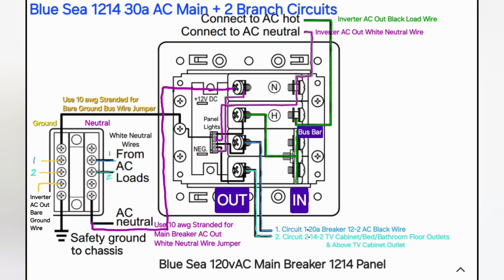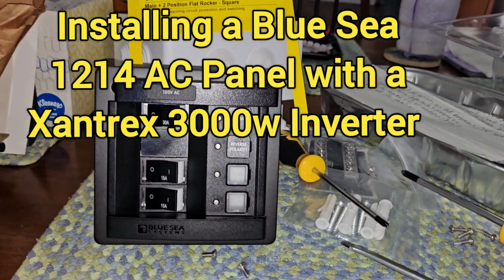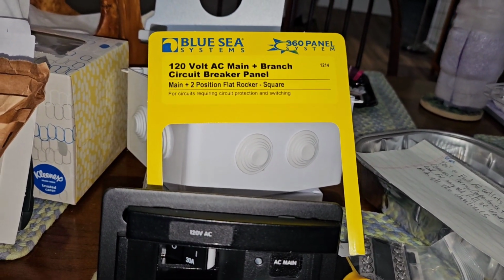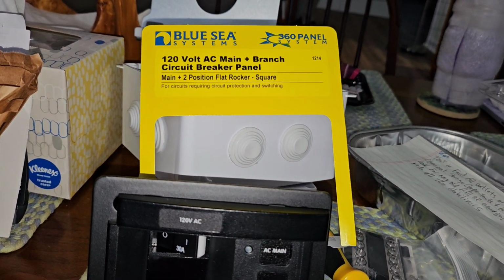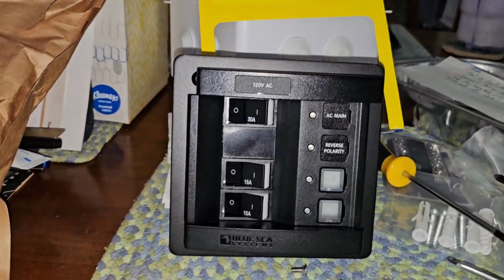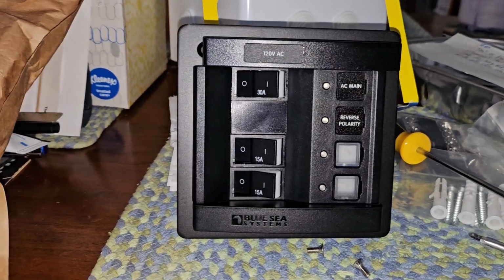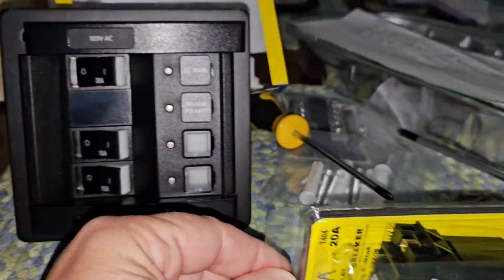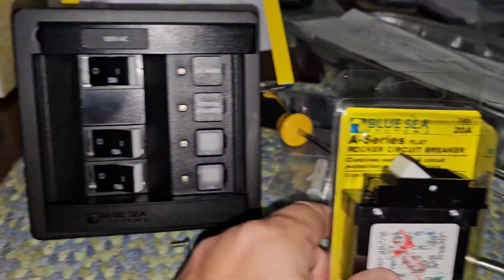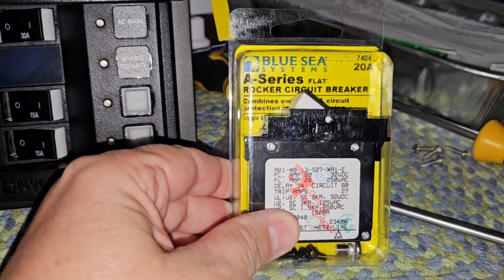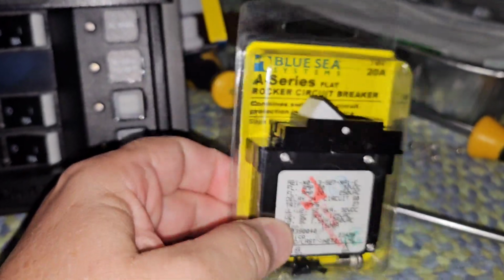I selected the Blue Sea 1214 AC panel because it's very compact and provides a 30 amp main breaker and two branch circuit breakers of any size you choose, which I'm going to use as a 20 amp and a 15 amp. I purchased this Blue Sea 120 volt AC main 30 amp breaker panel with two branch circuit breakers, and it comes with two 15 amp breakers, but I want to replace one with a 20 amp.